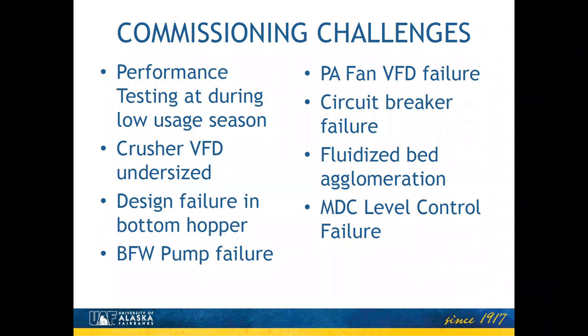We got past that one, and then we started ramping the boiler up when we had a failure of one of the boiler feed water pumps. And this plant has two feed water pumps. The feed water pumps supply the water at the necessary pressure to the boiler to keep it from overheating and to supply the right rate of water for steam production. And we have two of them so that if one does fail, the other one catches it right away. There's a third one installed in the plant that is there strictly for emergencies. If the plant were to lose electricity that drives these pumps, then a steam-driven pump would kick on and allow the boiler to safely shut down. But one of the electric pumps failed, and we ended up having to send that back to the manufacturer and getting that reworked, and we've got it back in service now.